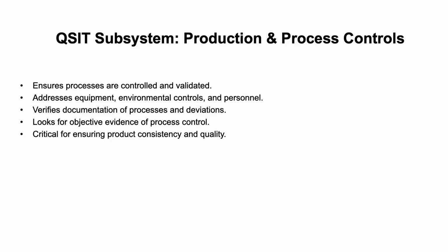For example, if a manufacturer uses a sterilization process, the FDA will want to see validation records that prove the process consistently sterilizes the device without damaging it. This is crucial for ensuring that every unit of a medical device is safe and effective.